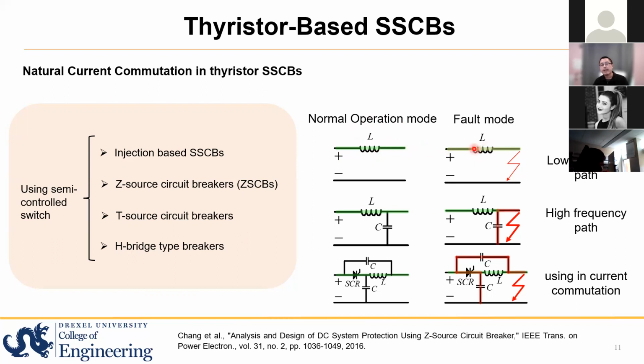And then if we have a fault, let's say a line-to-line fault, it means the high voltage line has a huge fault current flowing to the ground or to the negative of the line. And this is a normal, we call it a low frequency path, because this inductor in the DC system usually is super large. It's in the millihenry range. And then for the high frequency path, you could see usually in the DC system we have a capacitor to support the DC bus voltage. And if we have a fault at the load side, we could see there's a discharge of this capacitor, and this discharge is a high frequency path.